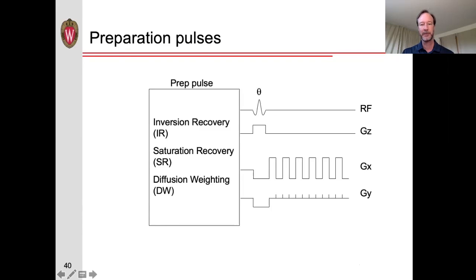So these preparation pulses can also be used to give us additional contrast in our imaging. For example, we can do inversion recovery, or saturation recovery, or diffusion weighting. What these pulses are, are basically additional RF pulses that are played before you actually begin your data acquisition. In this case, as illustrated here, an echo-planar imaging acquisition.